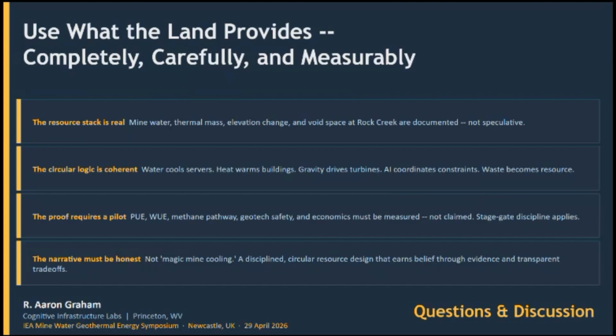I wanted to close with the same discipline I opened with. The resource stacks at Rock Creek and at hundreds of abandoned mines across West Virginia are real, documented, permitted, and the circular logic is coherent. Water cools servers, heat warms buildings, gravity drives turbines. But the proof requires a pilot. PUE and WUE, methane pathway, geotechnics, safety and economics must be measured. The narrative must be honest. This is not magic mine cooling. This is disciplined circular resource design that earns belief through evidence. Thank you.